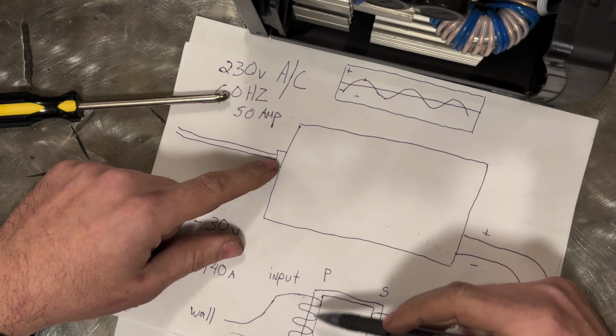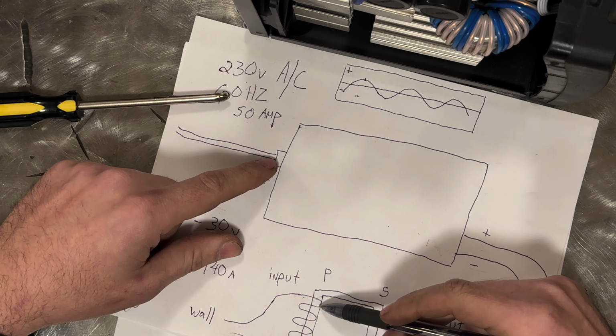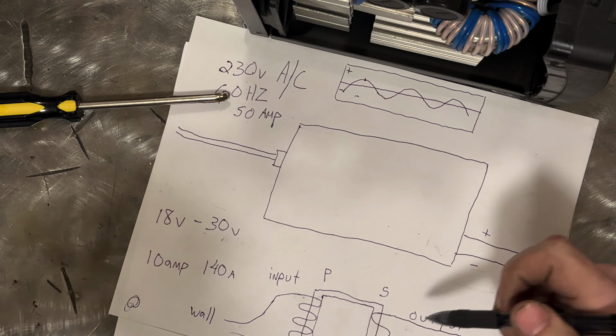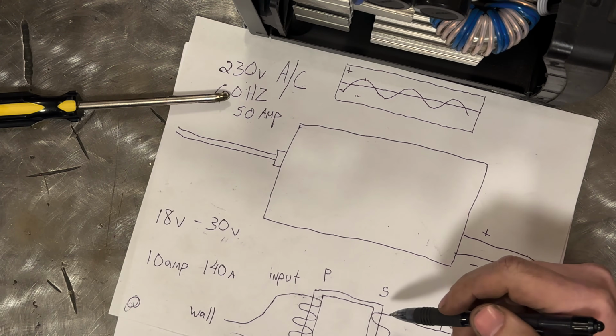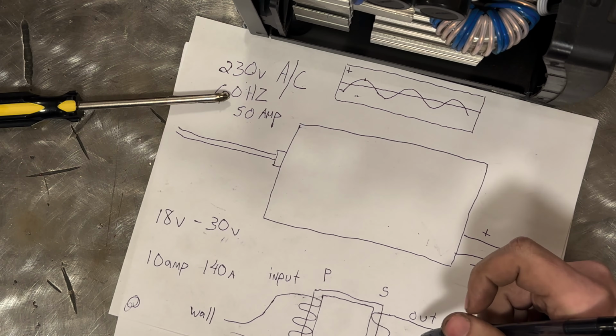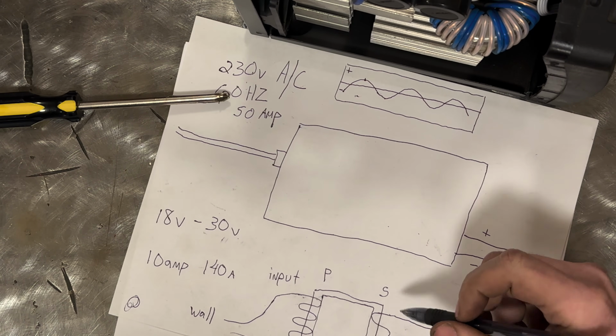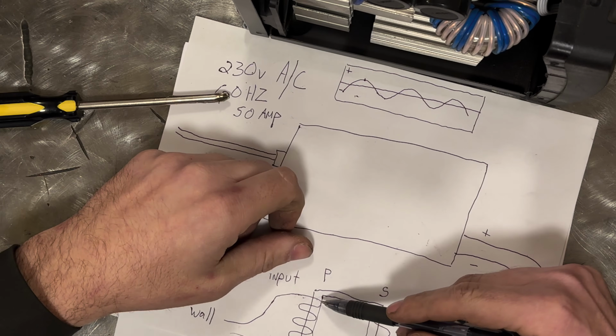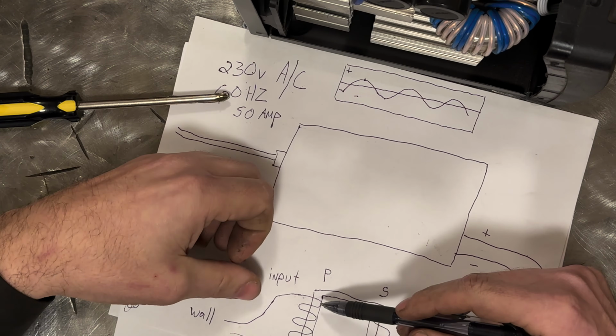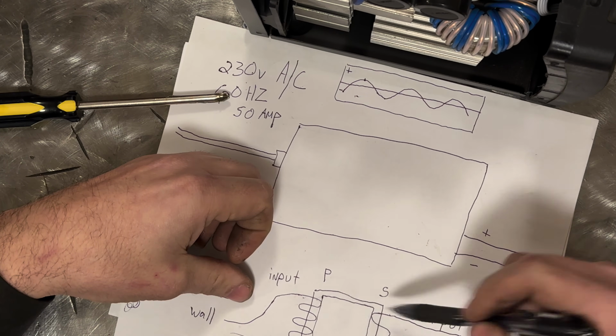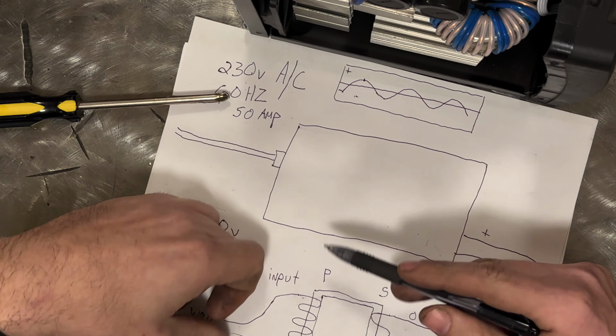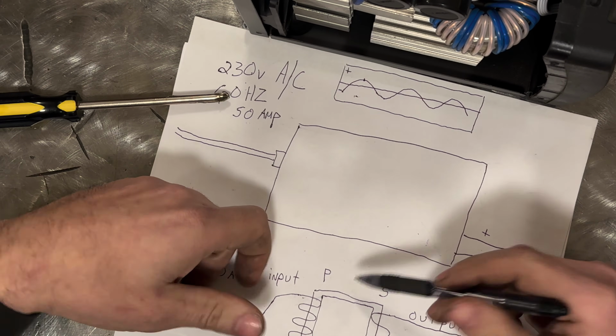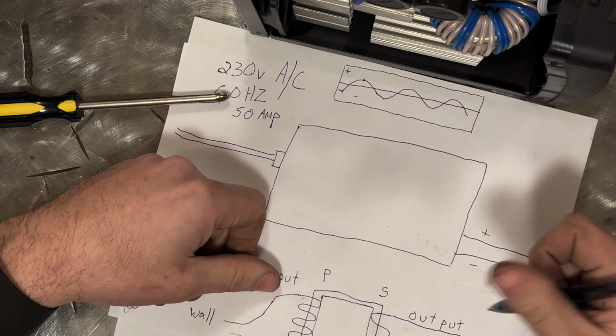So if you had, say, 10 wraps on the primary side and 5 on the output, that's a 2 to 1 step down. So you would lower your voltage from 10 to 5 — at 220 volts, you'd step down to 110 on the output.